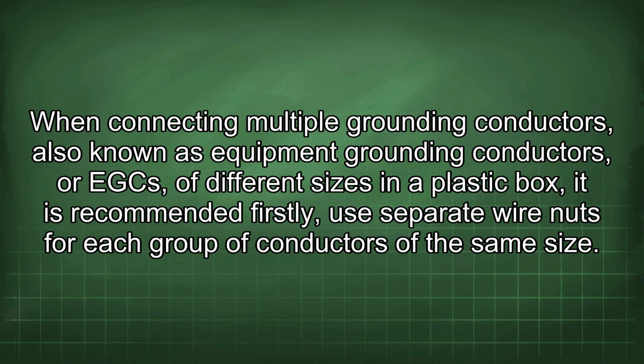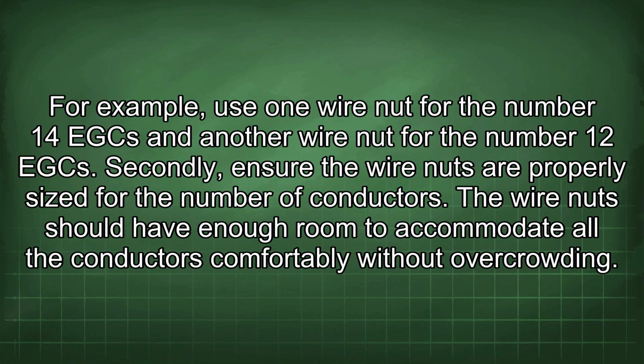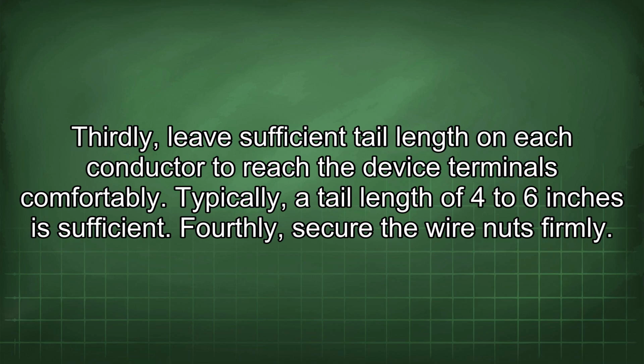it is recommended, firstly, use separate wire nuts for each group of conductors of the same size. For example, use one wire nut for the number 14 EGC and another wire nut for the number 12 EGC. Secondly, ensure the wire nuts are properly sized for the number of conductors. The wire nut should have enough room to accommodate all the conductors comfortably without overcrowding. Thirdly, leave sufficient tail length on each conductor to reach the device terminals comfortably. Typically, a tail length of 4 to 6 inches is sufficient.